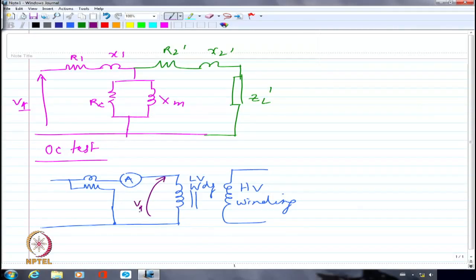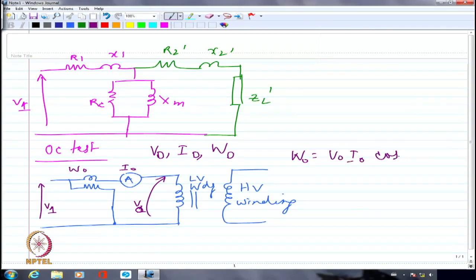So what I get as the reading will be V1, I1 and maybe W1. Rather, I named these as V0, I0 and W0 to specify that this is the no load condition. So I'm going to show this as I0 and this as W0. And of course, the voltage applied here is the rated voltage. It may be very difficult for me to find the rated voltage if I choose the high voltage winding to be excited. That's the reason I'm conducting this test by applying the voltage on the low voltage side, just for logistics reasons. And then we got W0 equal to V0 I0 cos phi naught. So I should be able to get exactly cos phi naught, the no load power factor.